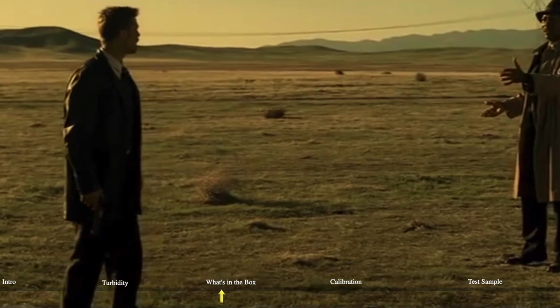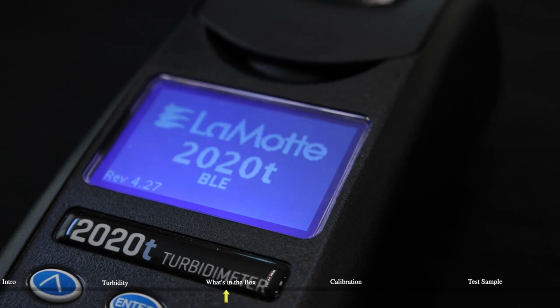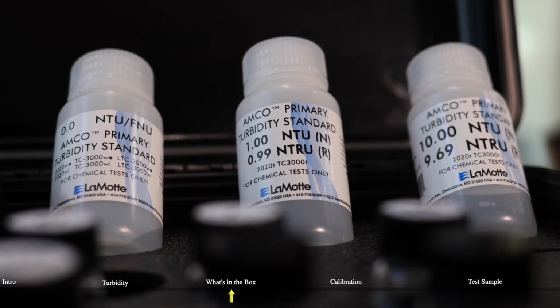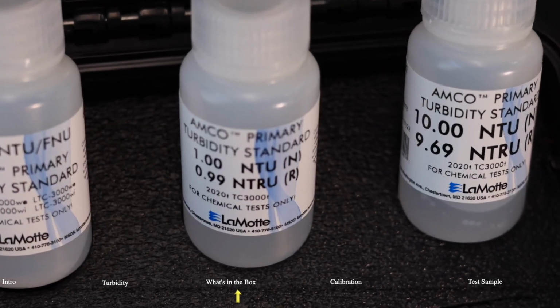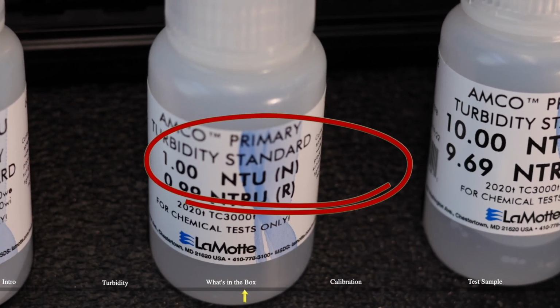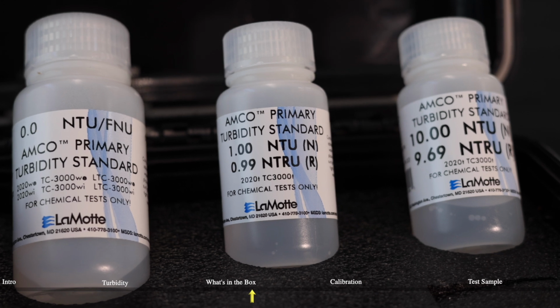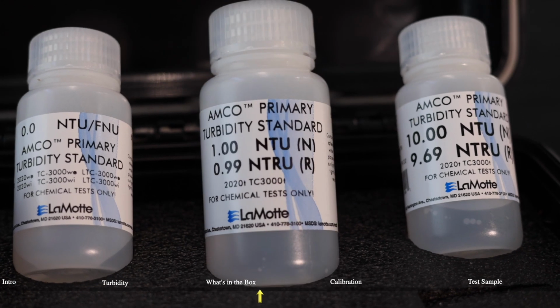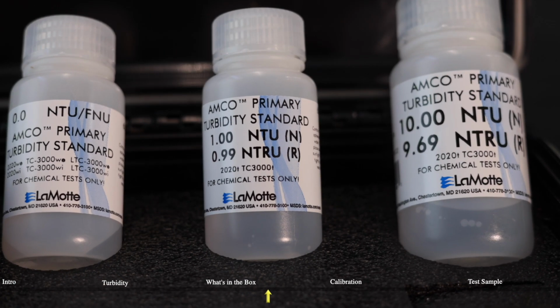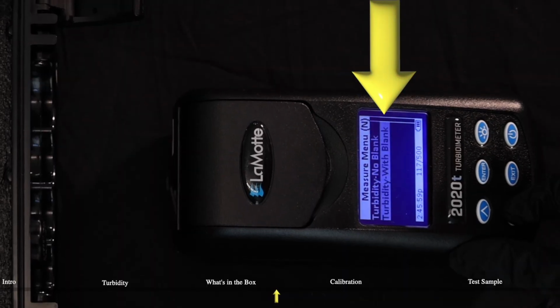So I know you're wondering, what's in the box? Inside this box you will find your meter, 3 bottles used to hold your calibration fluids, aka standards. These fluids range from 0.0 NTU, which we'll call blank, to 1 NTU and 10 NTU. These are strictly for calibrating the meter.